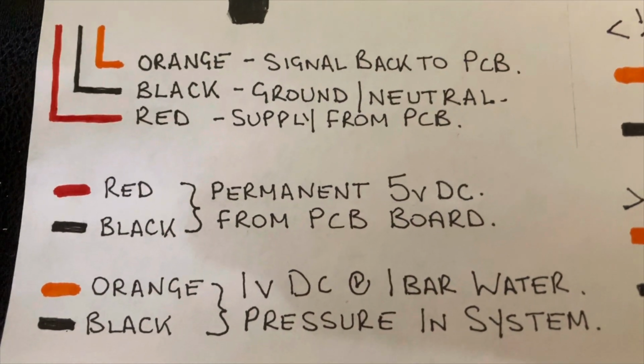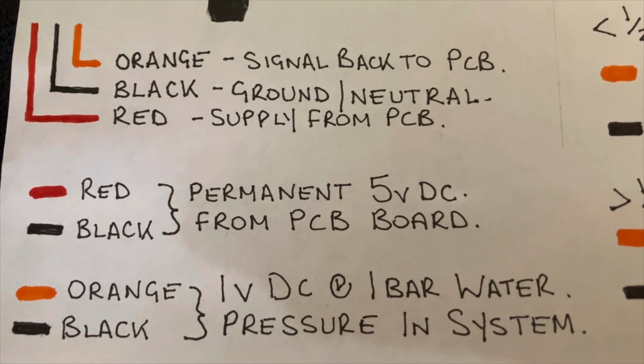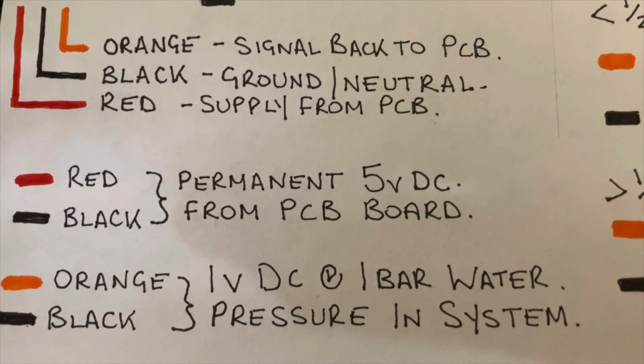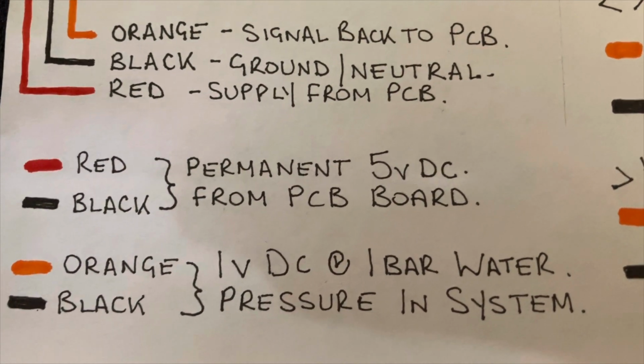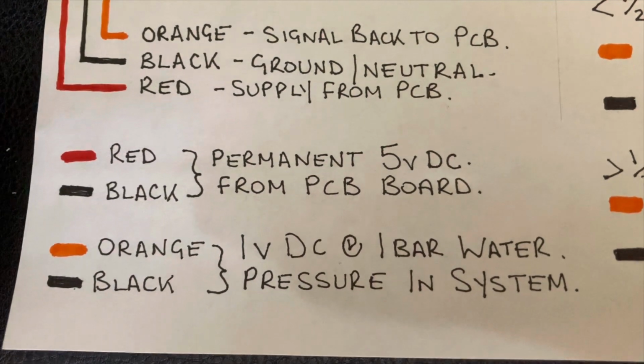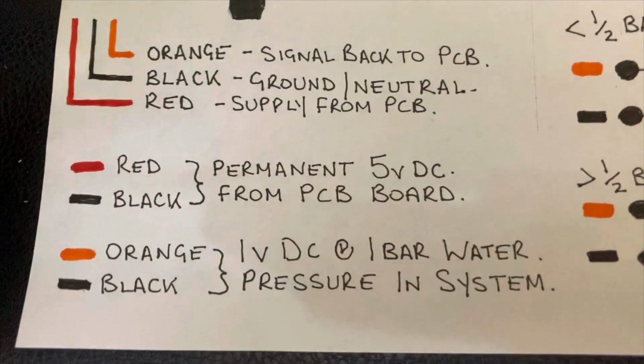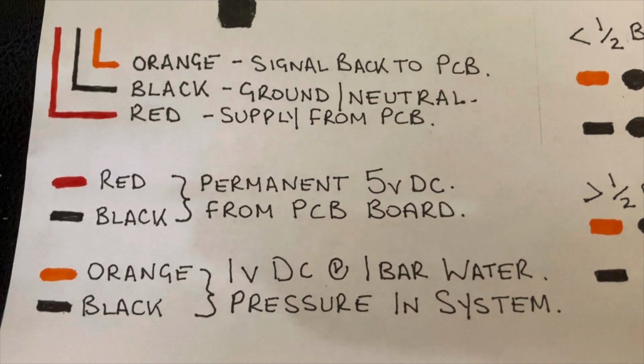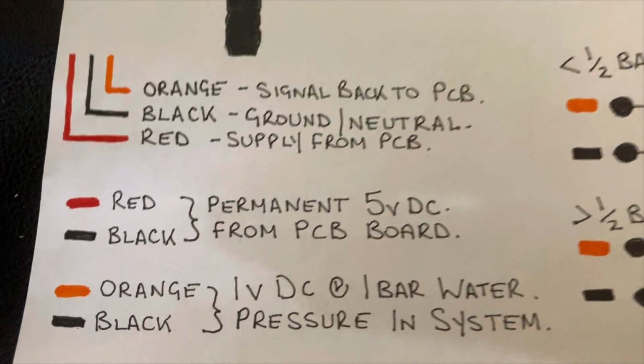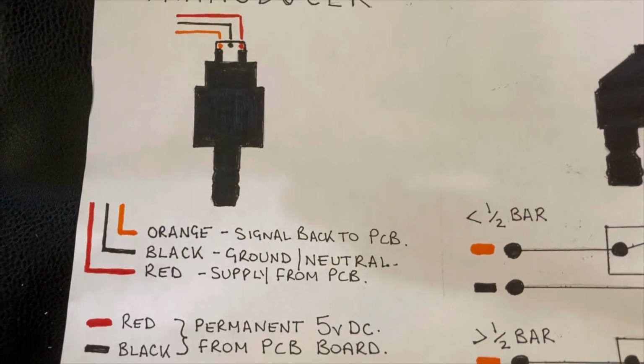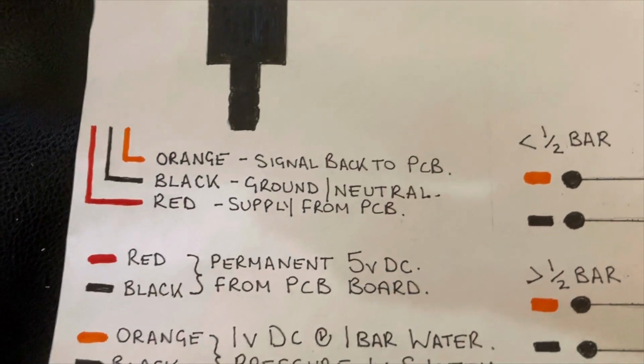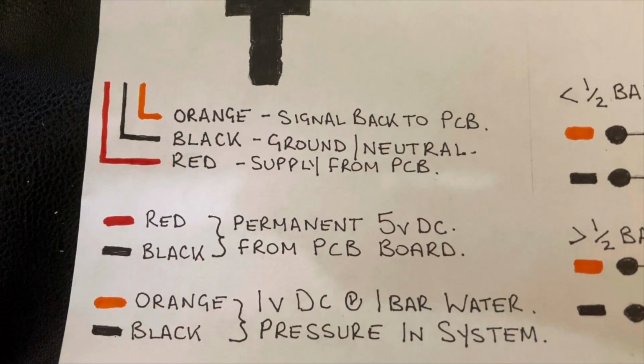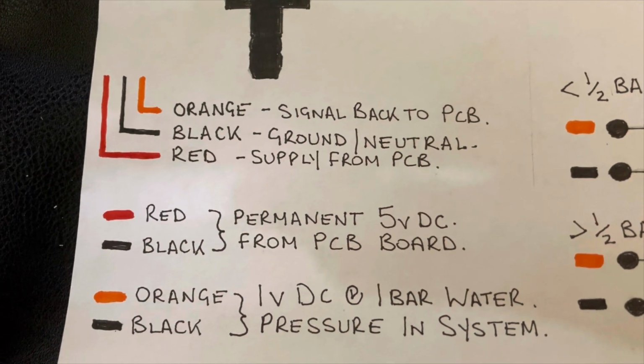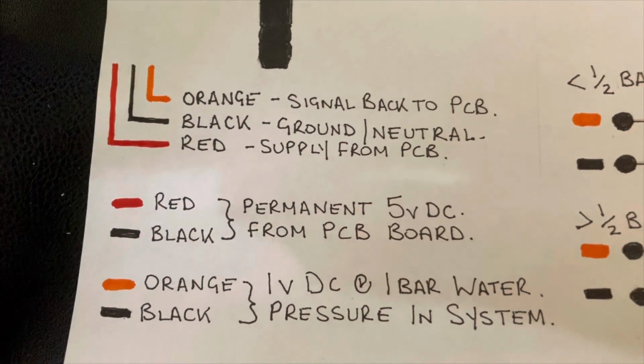Again, testing between orange and black, you'll get 1 volt DC at 1 bar of water pressure in the boiler, or in the system should I say. So you've got 1 bar in your heating system, you should get 1 volt DC signal back if this transducer is working. If the transducer fails, you'll probably just get 5 volts back on the orange and black, or 5-6 volts or something back.